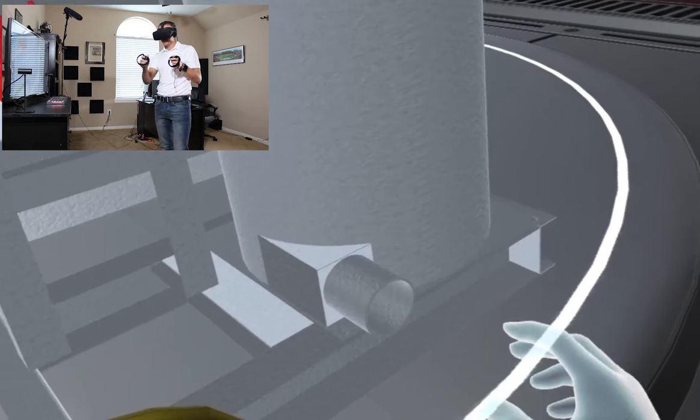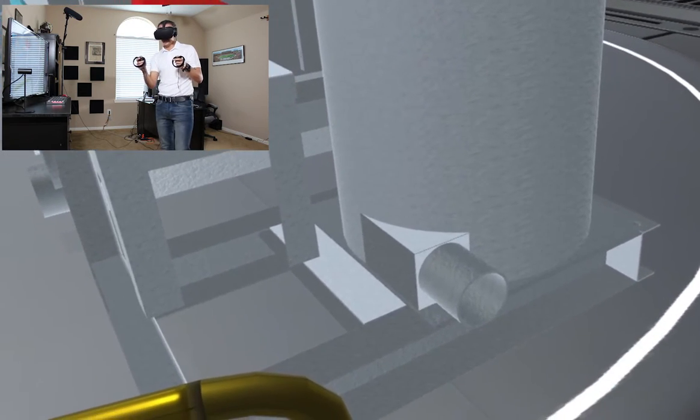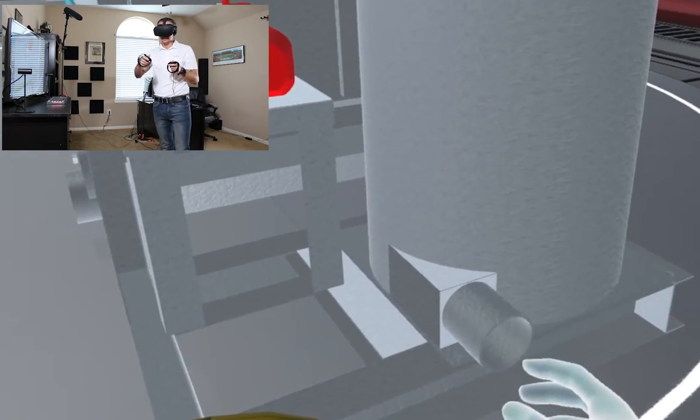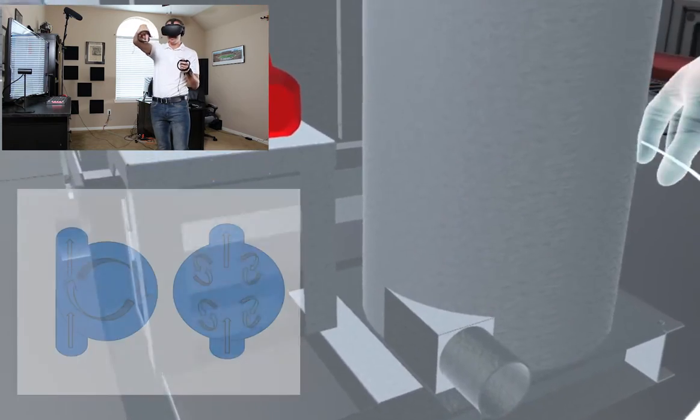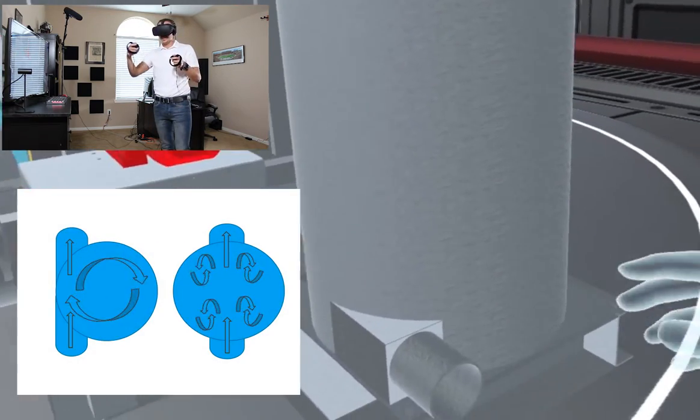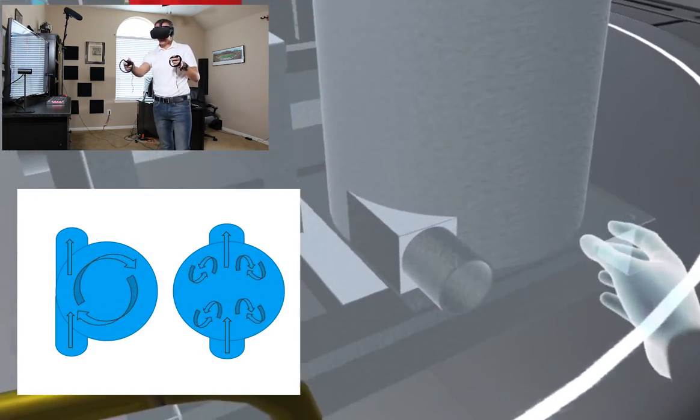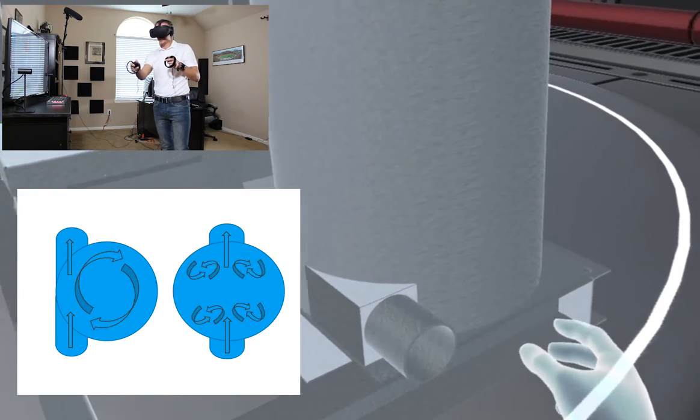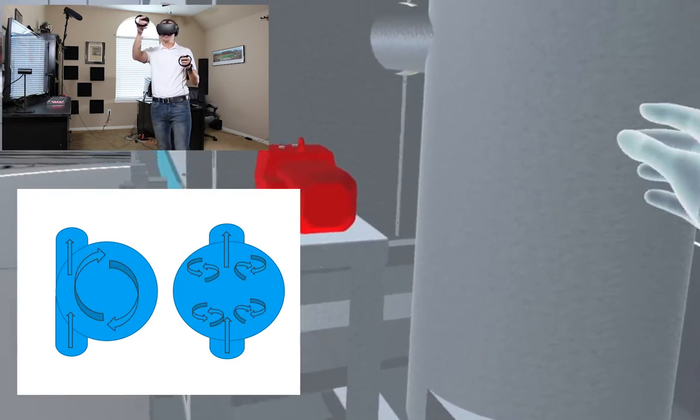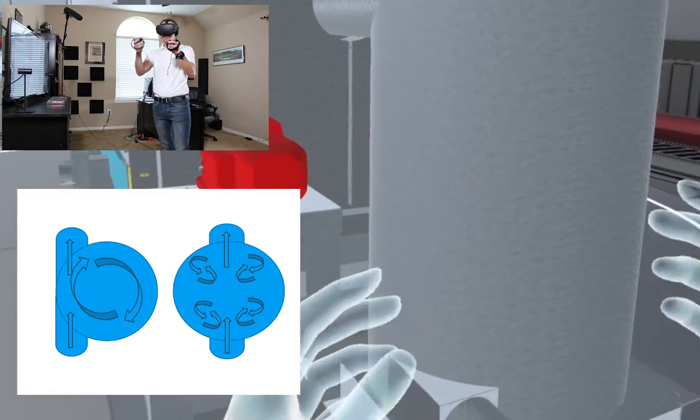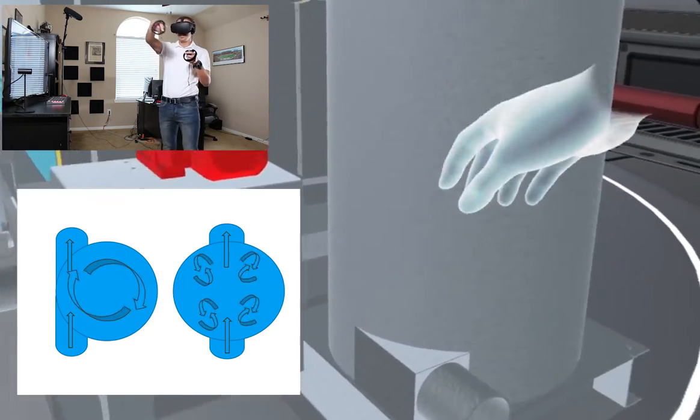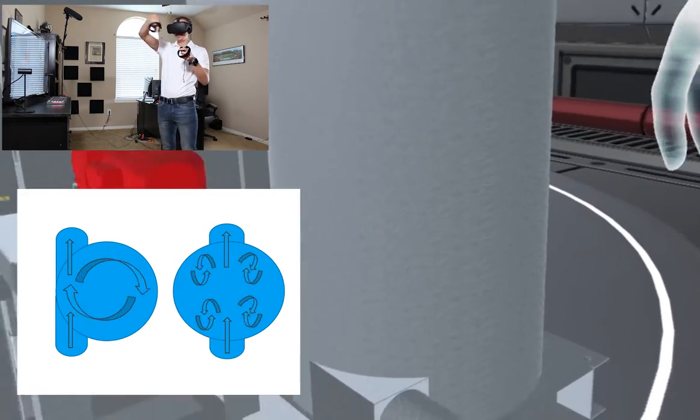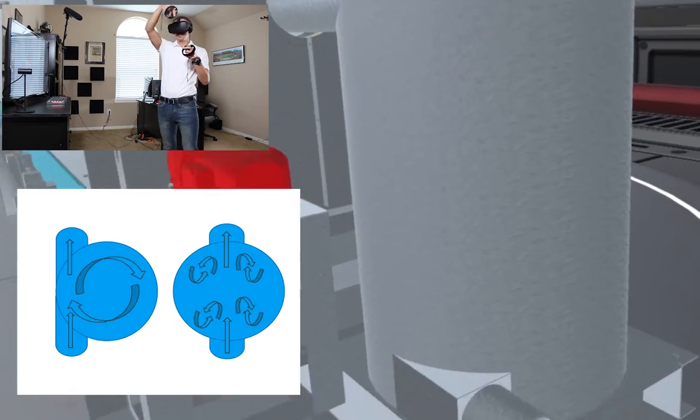What this does is it removes any sort of shear as the sludge comes into the tank, and it induces a cyclical motion going up. So if we had a tank that had just a perpendicular entrance on it, and it came in and shot up the tank and then out into the drum, you wouldn't have nearly as much residence time as you do with that circular cyclical motion as the sludge comes up.